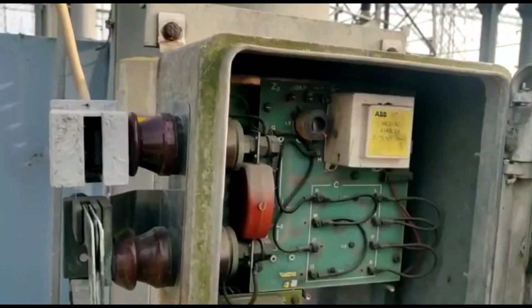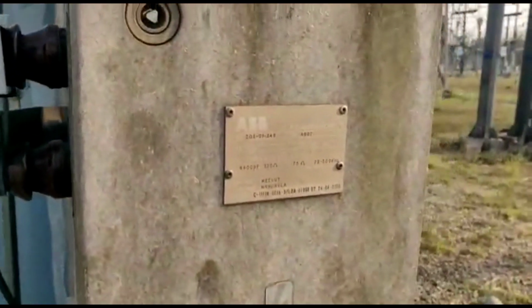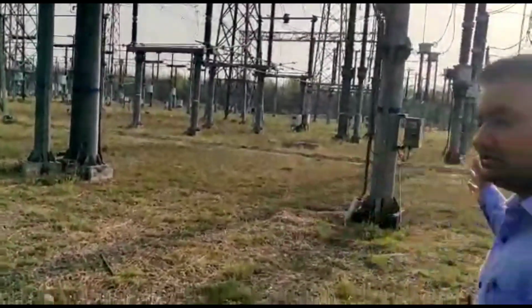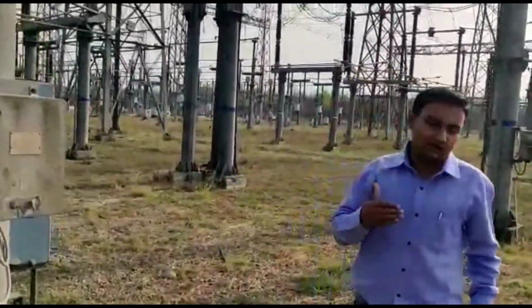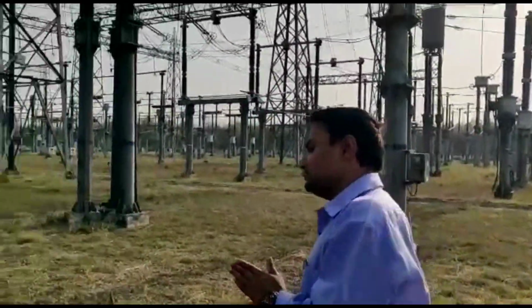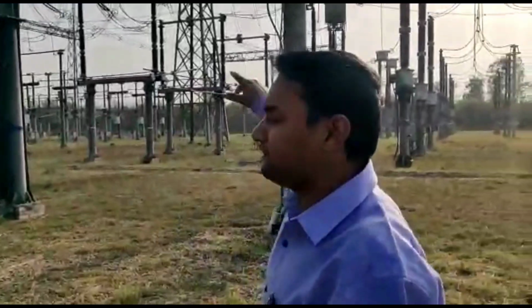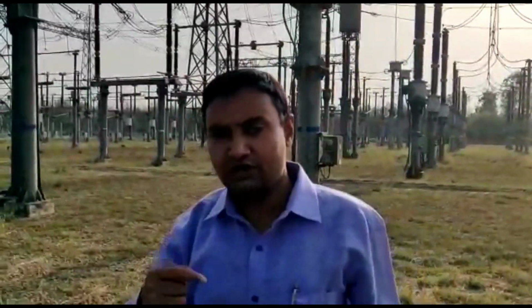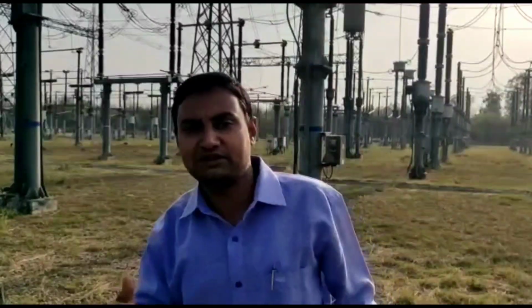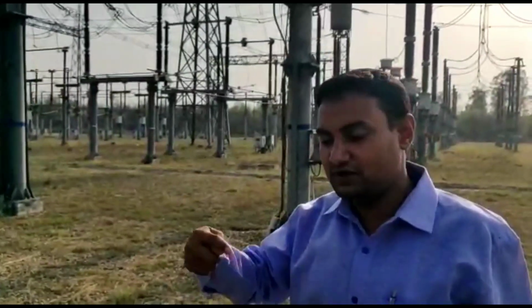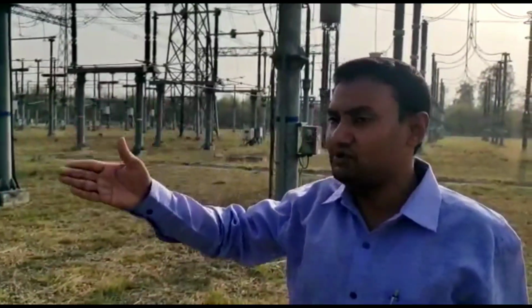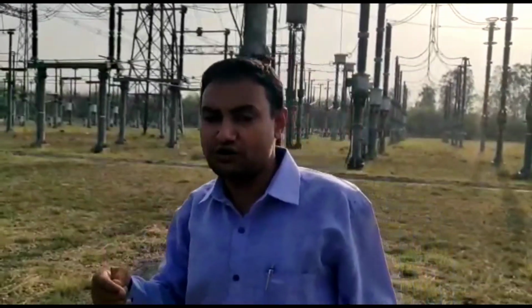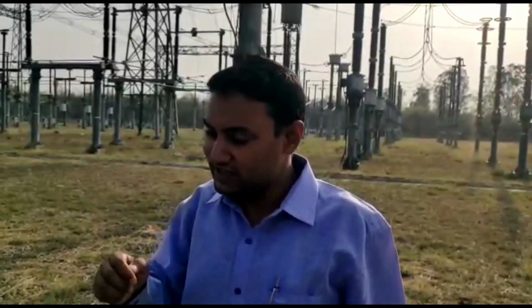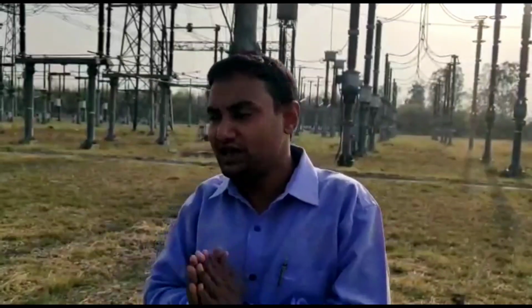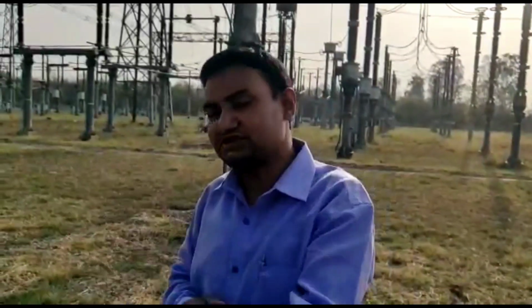Then the next thing, if you see here, these LMUs are installed in only two phases, and this is called phase-to-phase coupling. Why are we using phase-to-phase coupling? Suppose you are using this LMU and wave trap complete setup in only one phase, then it is one phase and ground, which will be a phase to ground coupling. But the disadvantage is that if there is any fault on that particular phase, suppose this LMU is used in Y phase and we are using Y phase to ground coupling, and there is a fault on Y phase itself, then there is a high probability that your signal might not be transferred from this substation to the next substation, and the PLCC system might not operate properly.